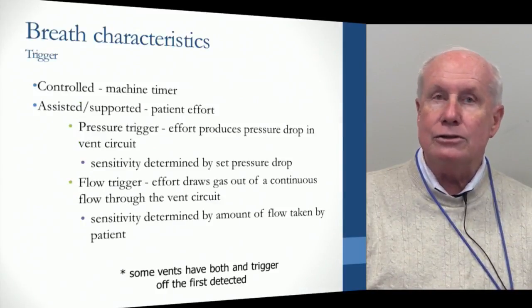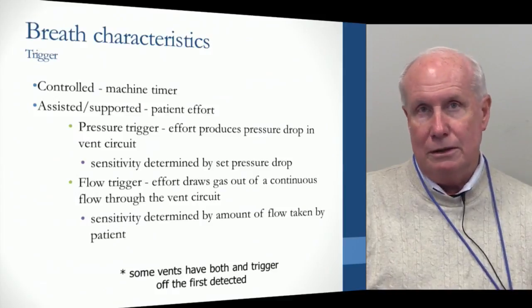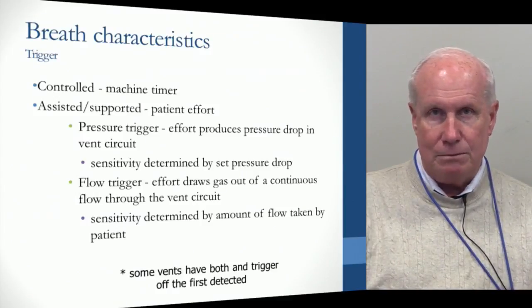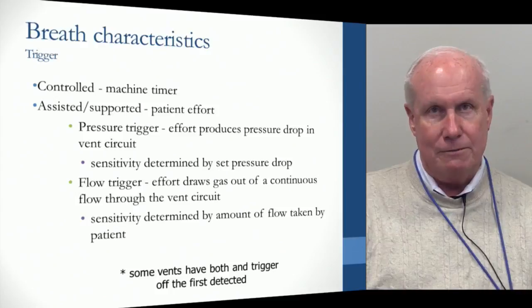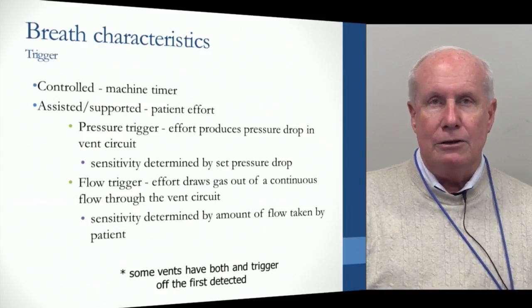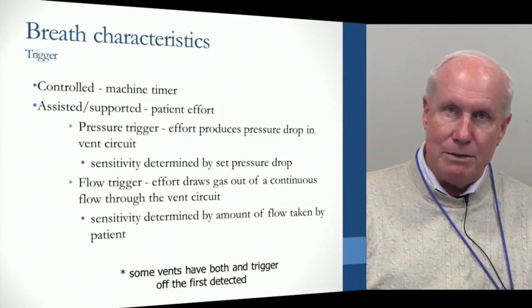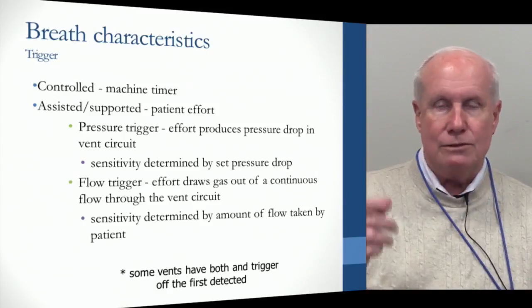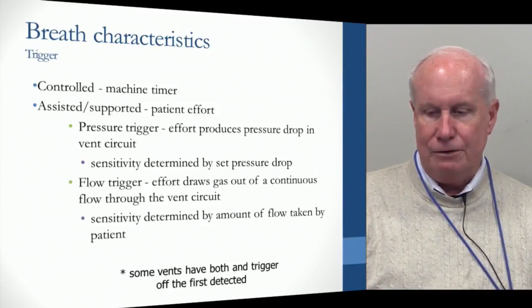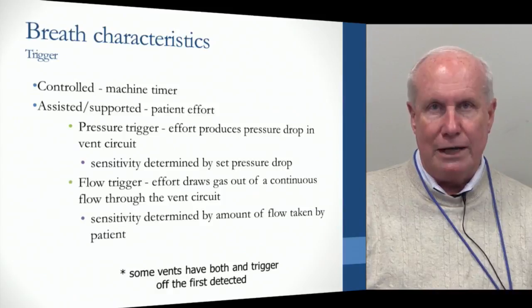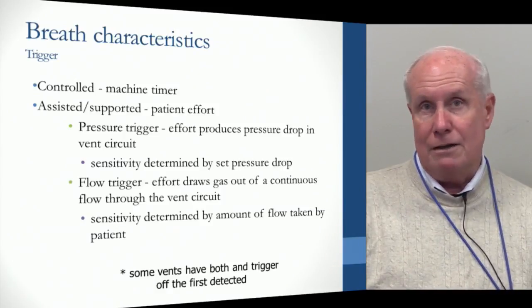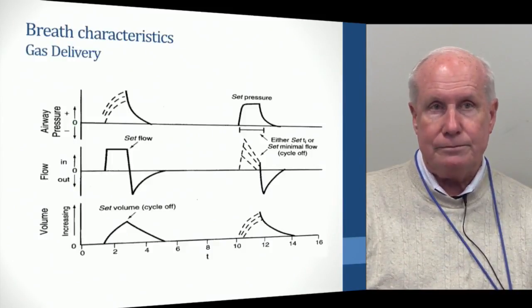So again, triggers, controlled or assisted. And we talk about pressure triggers. The patient makes an effort, the pressure drops, the ventilator fires. Another common assist trigger is when the patient makes an effort, it changes a continuous flow. The ventilator senses an effort and says, let's deliver a breath. And some ventilators, a lot of them actually, have both.